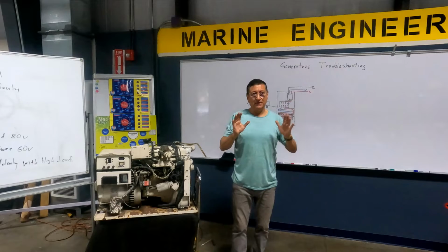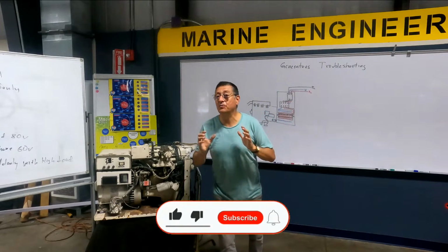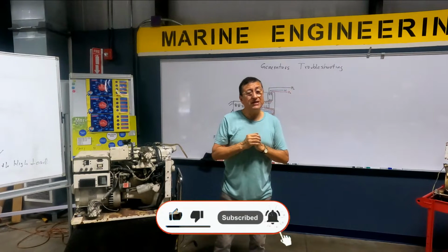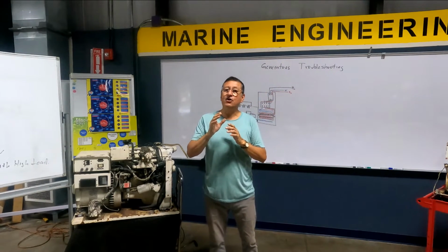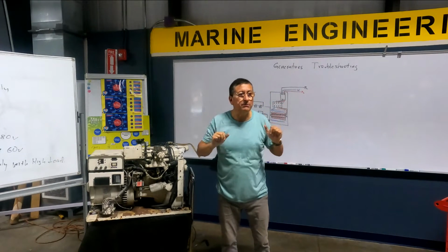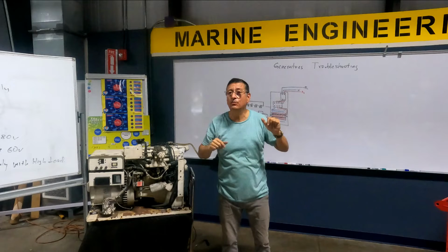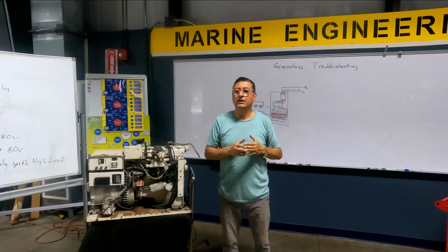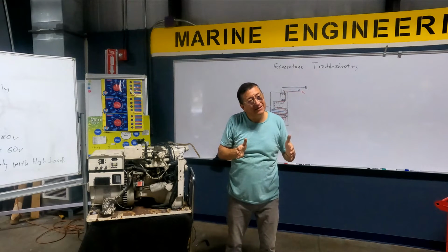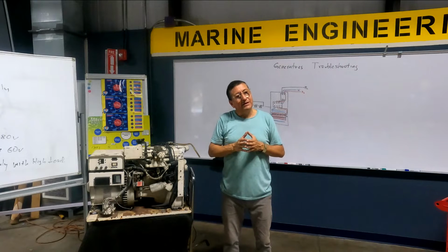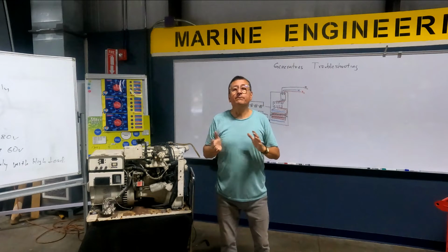In other words, if the complaint of the customer is about the engine, it is a DC problem. If the complaint of the customer is about the AC current, with the phases, with the AC output, it is a problem in the back end. And you divided the problem.